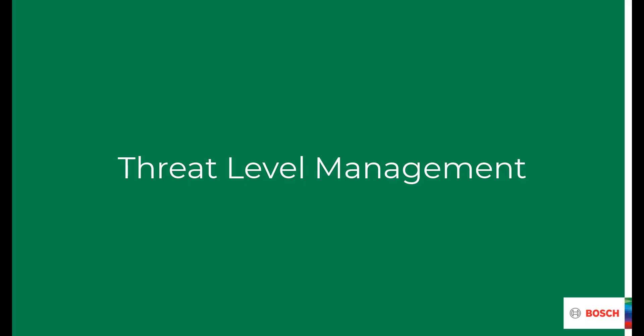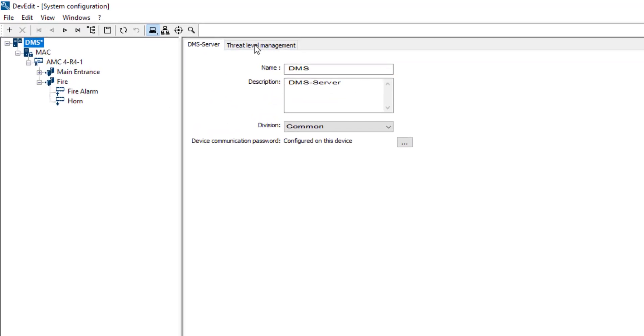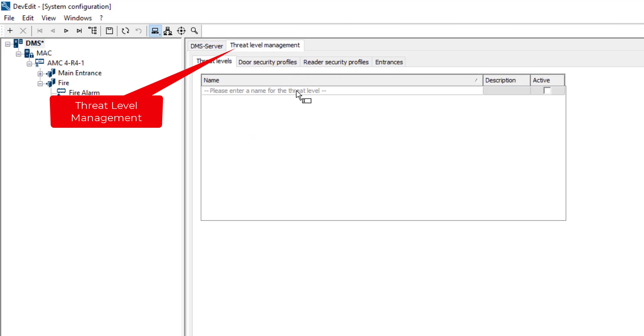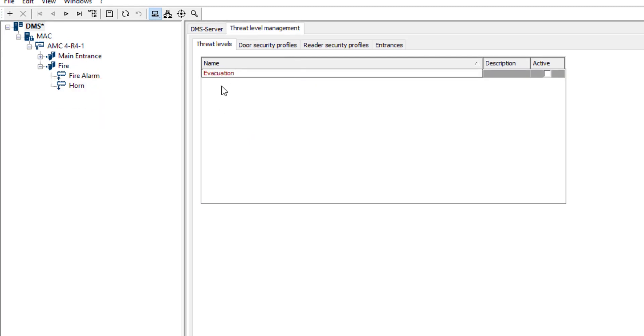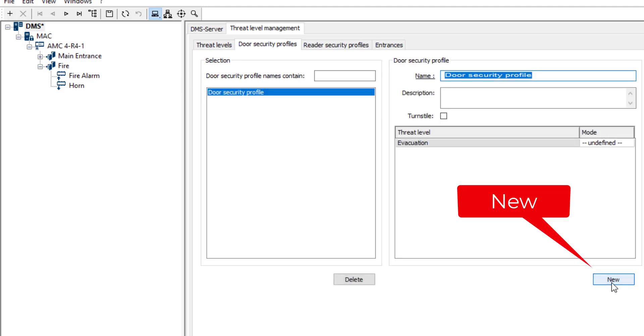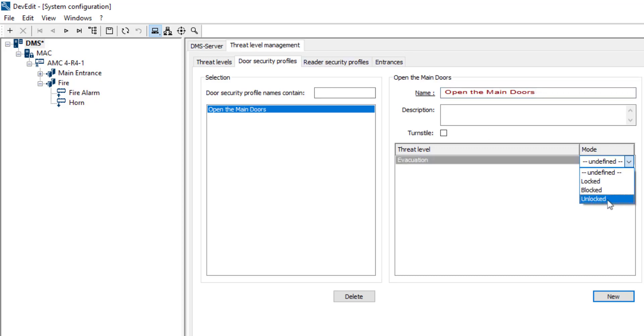Threat level management. A threat can come from the outside or from the inside. Typically when the threat comes from the outside, you want to block the outside doors. On the other hand, when the threat comes from within the building you want the doors to be opened to facilitate smooth evacuation. In the AMS system configuration we select the DMS entry, and then the page threat level management. The name of our threat level will be evacuation. We can immediately activate it. On the page door security profiles we will create a new profile and give it a self-explanatory name. The mode of this profile is unlocked. We want to unlock the doors.